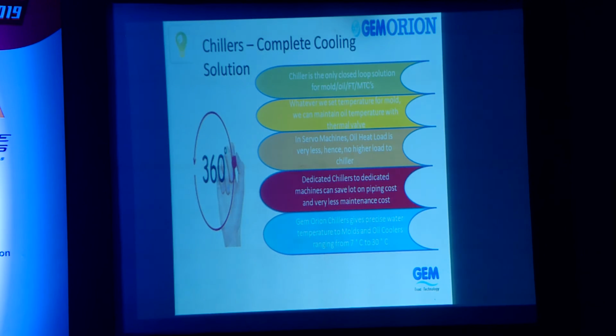Since current molding machines, most of the machines are coming with servo controlled power packs, the heat load is very less. Normally the conventional will be about 40-50% of the installed HP, whereas servos consume only about 12 to 14%, and it cycles as well. So we can directly load that into the chiller itself. So that is one of the ideas what is possible. Then dedicated chillers, as I told you, save on piping cost and have very less maintenance cost, and one-to-one communication is possible, so when machine is off, chiller can be off. Our Japanese models have very precise controls, delivering temperature of plus or minus 1 degree. It can maintain any set point temperature from about 7 to about 30 degrees.